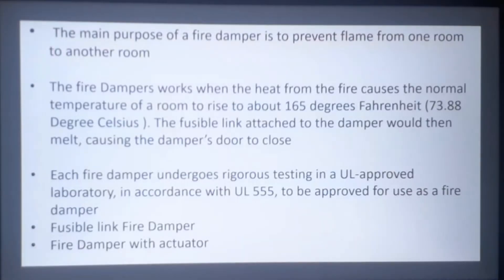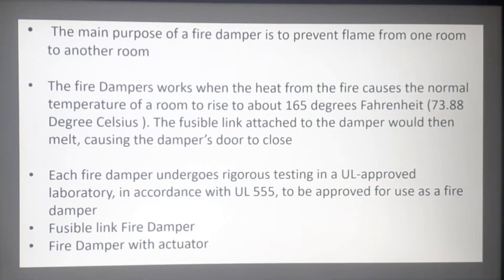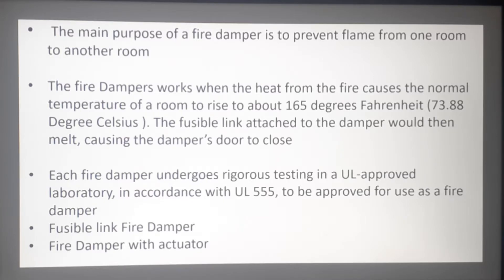When buying fire dampers, the first thing to check is whether it is UL certified — tested in a UL-approved laboratory — and whether it is in accordance with UL 555, which is the relevant standard. If it is tested and certified, then you can use it as a fire damper.